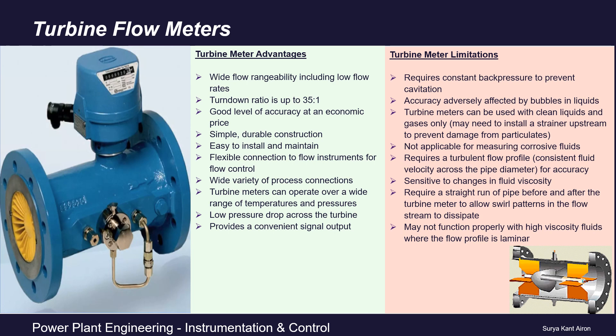They require a turbulent flow profile with consistent fluid velocity across the pipe diameter for accuracy, and are very sensitive to fluid viscosity. They require a straight pipe section before and after the turbine meter to allow any swirl pattern in the flow stream to dissipate. In the case of high viscosity fluids, they may not function properly.